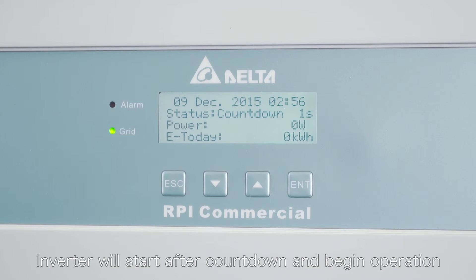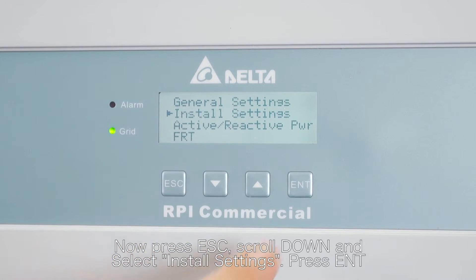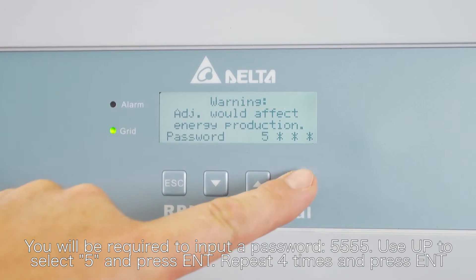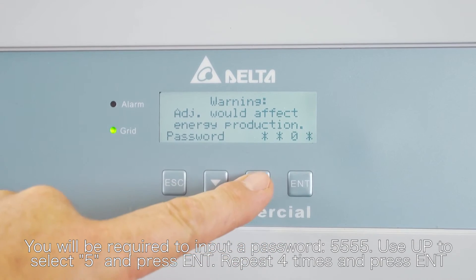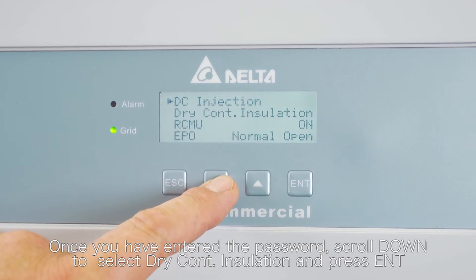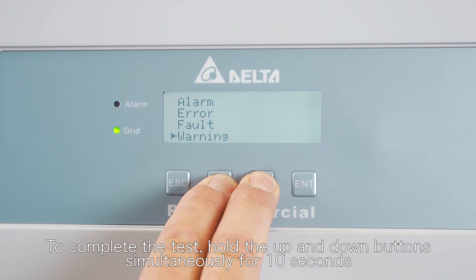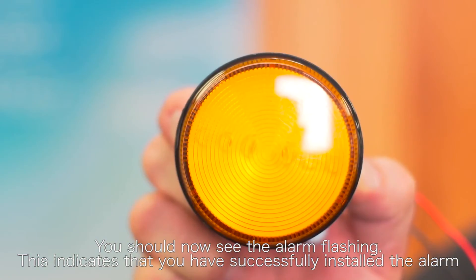The inverter will start after countdown and begin operation. Now press escape and scroll down and select installation settings and press enter. You will be required to input a password: 5555. Use the up key to select 5 and press enter, repeating 4 times then press enter again. Once you have entered the password, scroll down and select dry contact insulation and press enter. To complete the test, hold the up and down button simultaneously for 10 seconds. You should now see the alarm flashing. This indicates that you have successfully installed and tested the earth fault alarm.